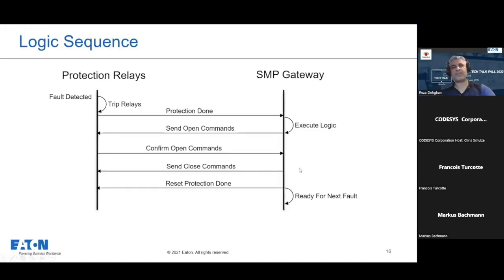Next one, the logic. So this is the logic sequence diagram, just the overview of what happens during a fault. On the left side, we have the protection relay. On the right side, we have the SMP Gateway. When the protection relay detects a fault, first of all, it trips the relay and it sends something that we call protection done. This basically says to SMP Gateway that everything is okay, the fault has been isolated. And then SMP Gateway starts to execute its logic, and it sends all the open commands to the relays. It waits for the confirmation of all those commands from the relay.